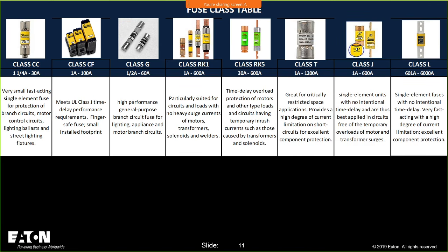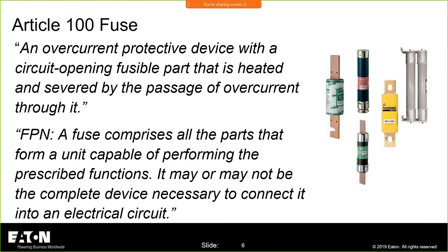So Roger pointed out a good, interesting point, and I'm going to go back. I'm going to go back in time. Article 100, fuse. Roger Zieg, yes, you pointed out an area that I thought was very intriguing recently, and I'm making a public input on this one as well for the 2023 cycle. Fuse is defined in Article 100. It's defined in Part 2. So to find the definition of a fuse, you have to go to Part 2, which is, let me make sure it's Part 2. Yep, Part 2, over 1,000 volts. And so, if you look at in Part 2, oops, somebody just took themselves off mute.